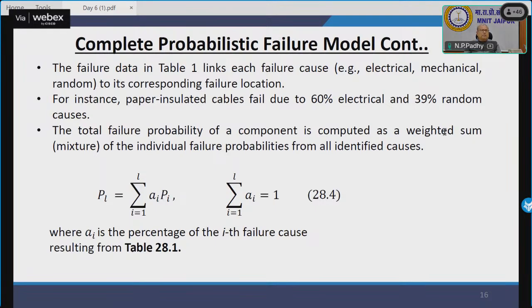For instance, paper insulated cable failed due to 60% electrical and 39% random causes. The total failure probability of a component is computed as a weighted sum mixture of individual failure probabilities from all identified causes: PL is the summation of AI times PI, where AI is the percentage of the ith failure cause, resulting from table 28.1, the next table.